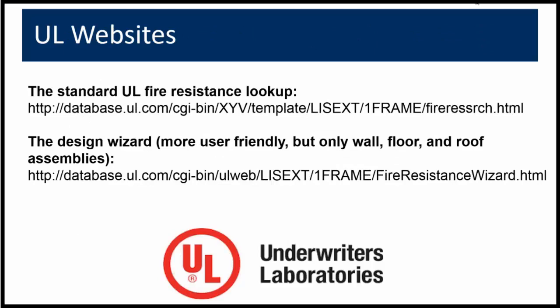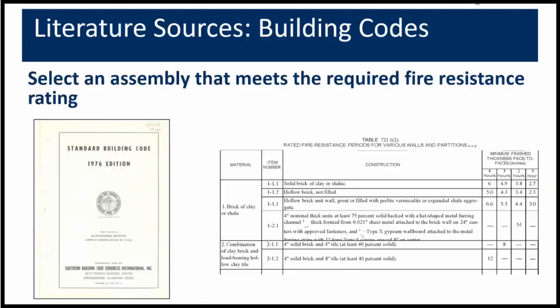Here's some information about the UL websites — we will also be posting these on the WJE portal for the fire protection TRG shortly. Another good literature source to select an assembly that meets the required fire resistance rating are building codes. The 1976 edition of the standard building code has an extensive appendix with listings of all types of assemblies, which is very useful, though that helpful appendix was deleted in the editions following 1976. The current 2015 edition of the IBC, Chapter 7, includes a list of assemblies and ratings which may be able to be matched to the assembly in question.